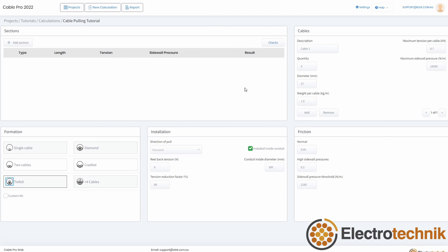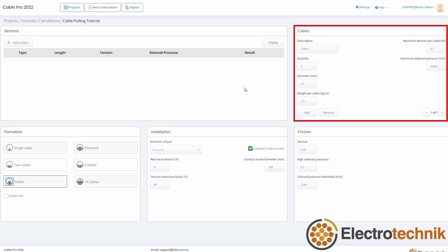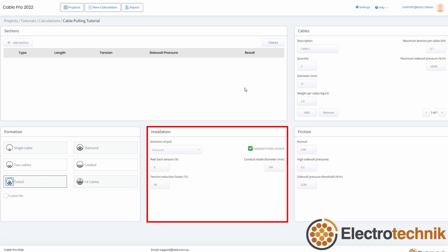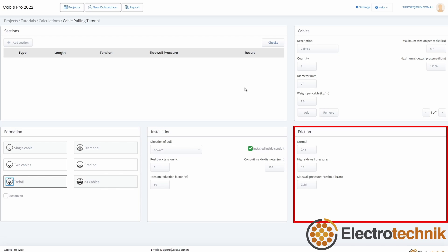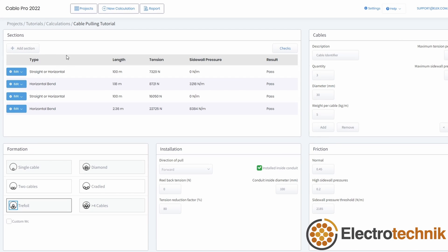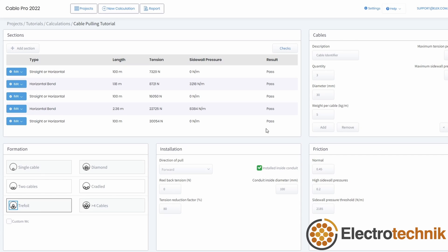Let's take a quick look at the main user interface. The cable section has inputs for cable data, such as data from the manufacturer datasheet and total number of cables. Multiple cable types can be entered into the calculator. The installation section includes conduit size and direction of the cable pull. The formation of the pull needs to be selected in this section. There is also a section for friction input. Once this data has been entered, sections of the pull matching your layout drawing should then be added.